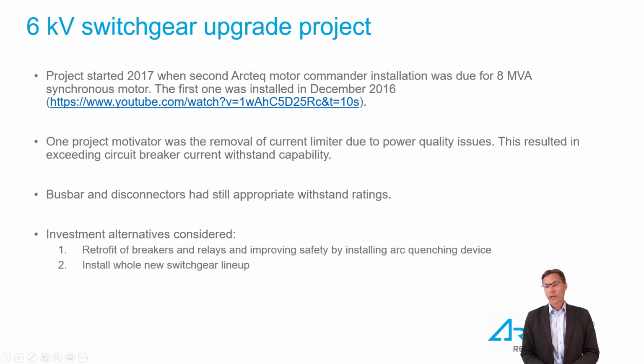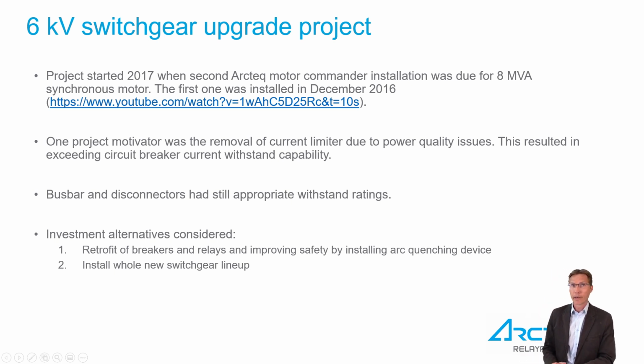This particular switchgear upgrade project was a 6 kV lineup, and Arcteq's first acquaintance in the plant was an installation of motor commander relays for protection and control of large synchronous motors. The first ones were installed back in 2016. This particular project was kicked off when another motor commander was due to be installed. And one of the motivators in the project was actually removal of the current limiter in the system.